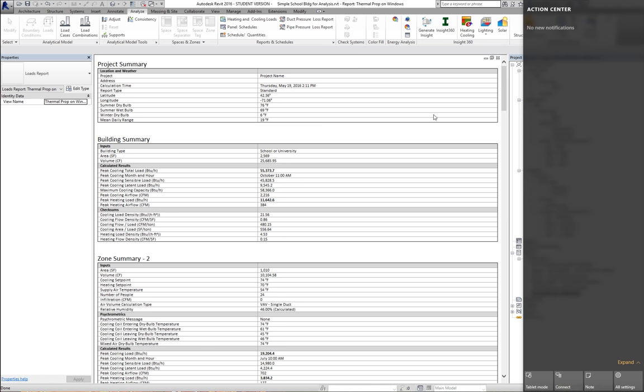Before we leave this, it's important to distinguish between peak cooling and heating loads versus total energy use. Peak loads determine how big the HVAC unit has to be — that's not a measure of how much energy is being used overall, just how big things have to be to handle that peak. If you really want to understand total energy use, you'd run the energy analysis to see cumulatively what the energy cost would be over 30 years. It's like determining the size of an engine versus understanding its average fuel consumption over your driving pattern.